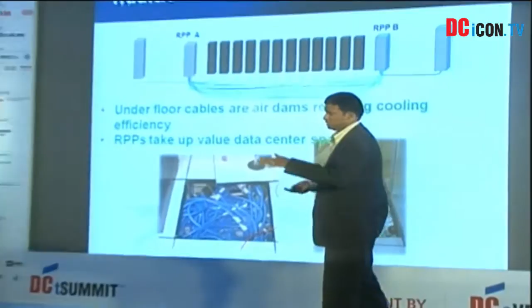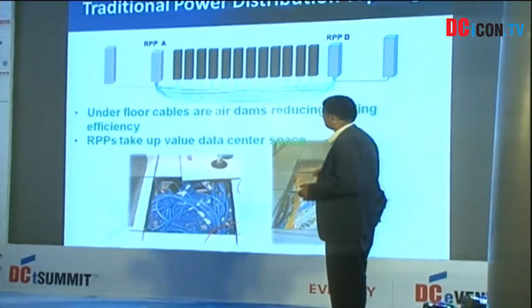Now when you do it below the raised floor, you have a challenge: the void space below gets completely choked, so the airflow is blocked. This reduces cooling efficiency, and when efficiency is reduced, power consumption becomes too high. So it's essential that these obstructions are eliminated.